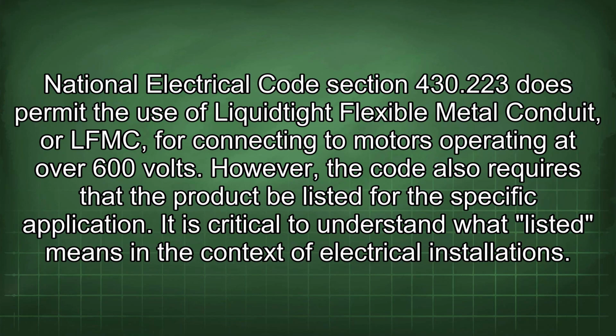National Electrical Code Section 430.223 does permit the use of Liquidtight Flexible Metal Conduit, or LFMC, for connecting to motors operating at over 600 volts. However, the code also requires that the product be listed for the specific application.